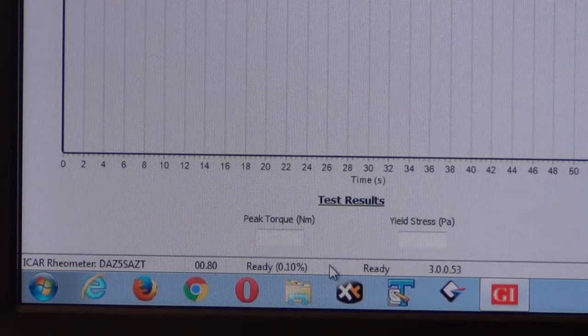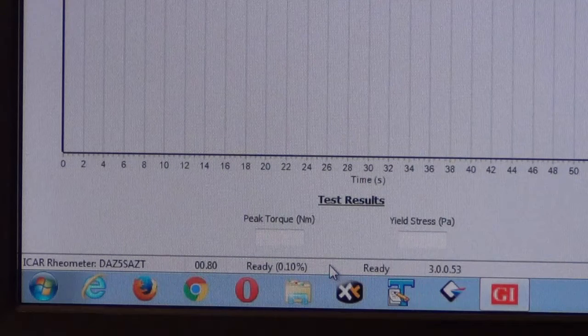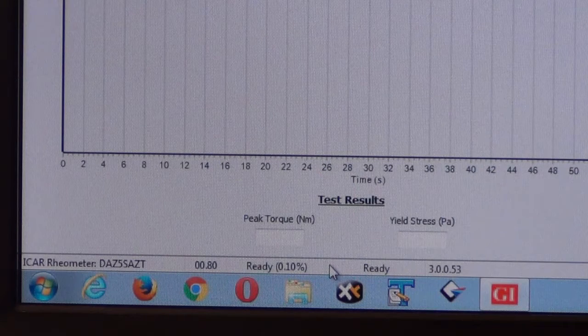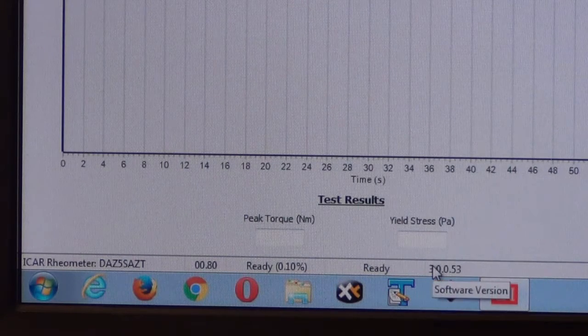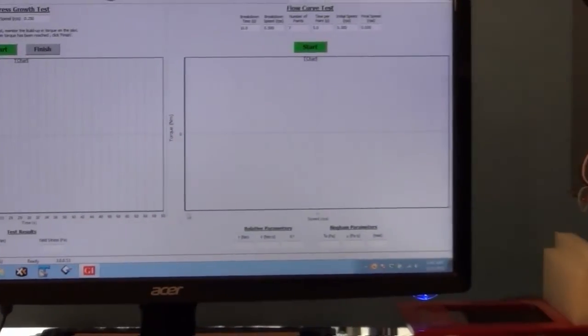The calibration information is very interesting because I took the numbers that we calculated earlier and I put them onto the system, and when the system powered up, the controller switched in the calibration resistor, acquired a reading, and compared it to the expectation we gave it based on our calculations from the calibration sheet. And they agreed within 0.1%, which is awesome. And the final cell is the software version, the user interface. So now we're going to go ahead and run the flow curve test.